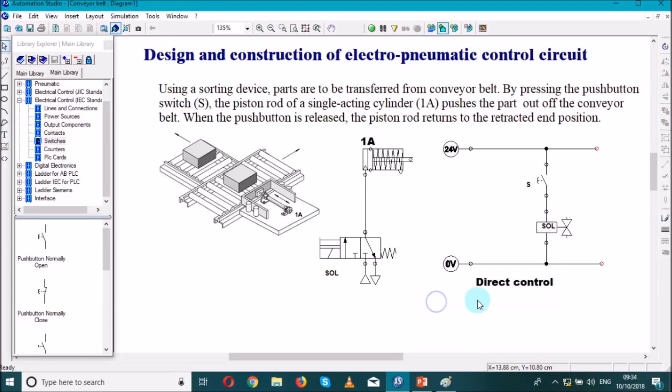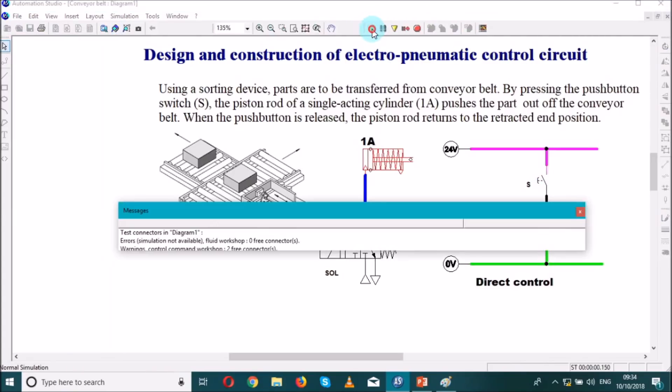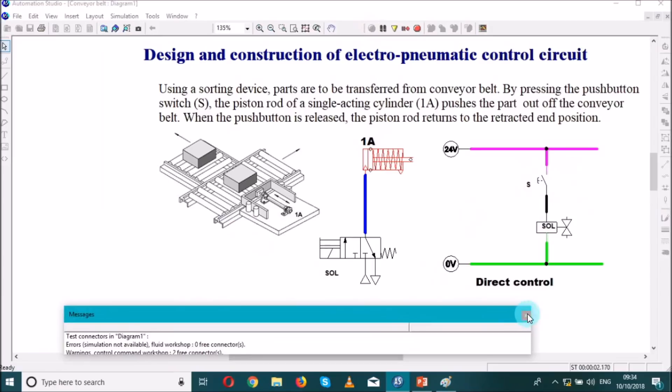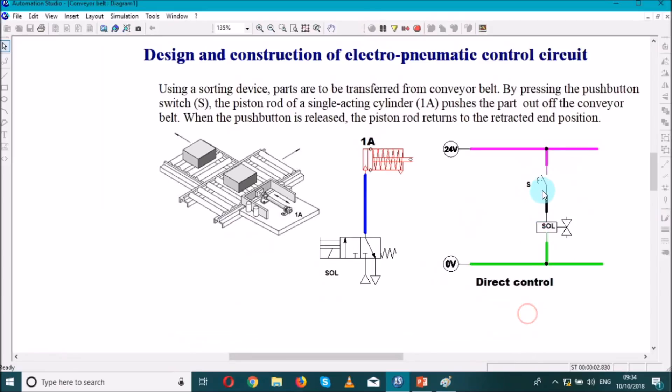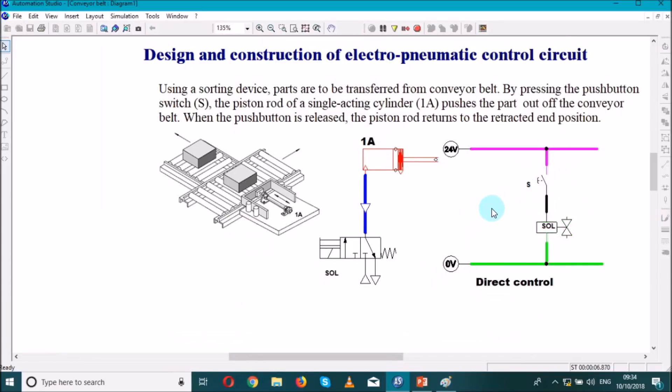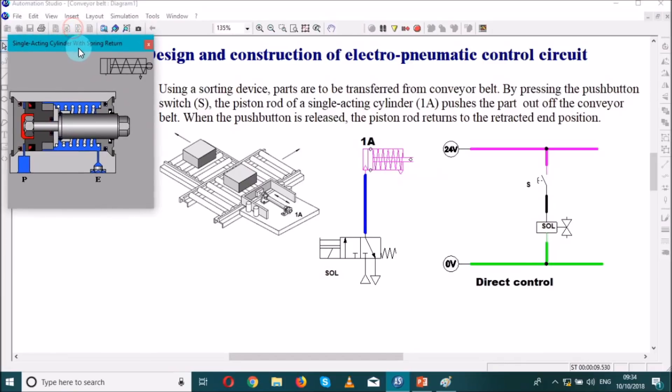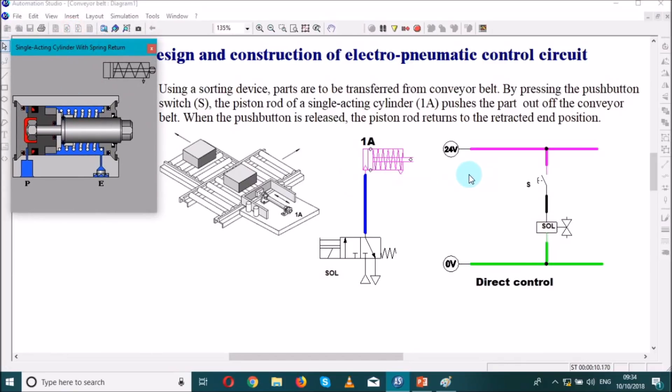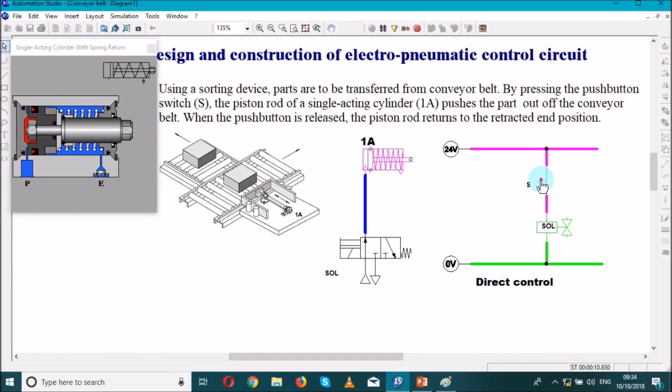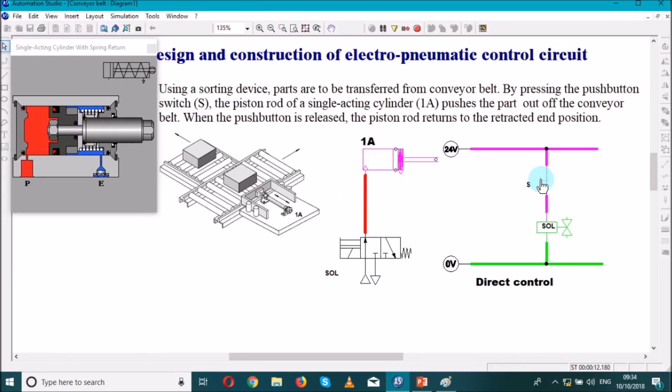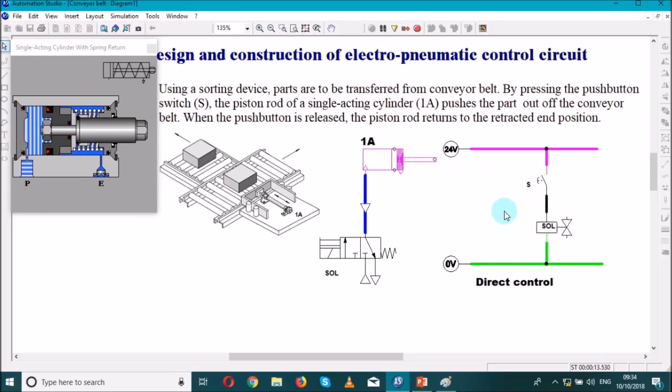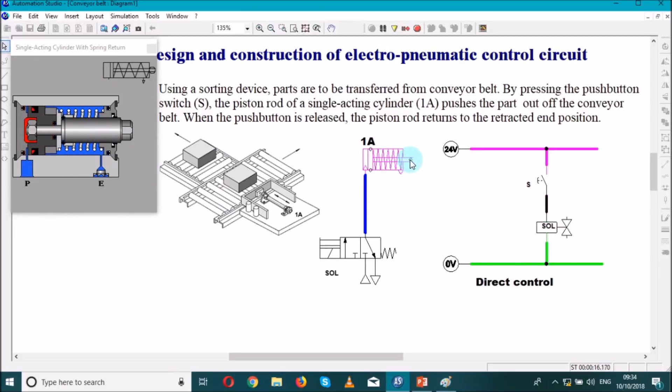We call it direct control because we don't have any contact here, we just have switch and the solenoid. So we simulate to see whether it works. By pressing the push button switch, the piston, the single acting cylinder has to extend. By releasing it comes back. So let's see what is happening inside. We press once again, the cylinder extends. The cylinder retracts back, so we have a spring there, that's why you call it single acting cylinder.